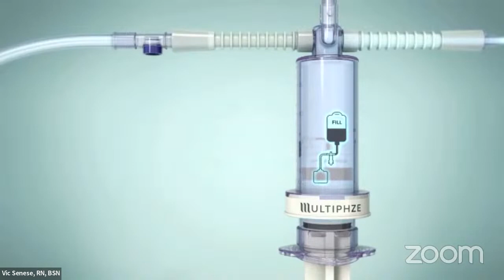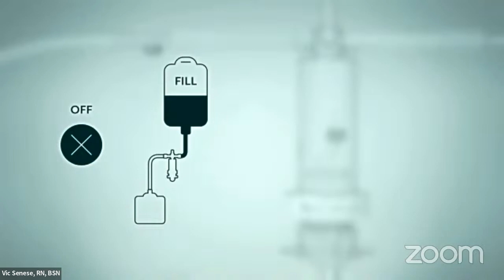The proprietary syringe has an augmented volume of 120 milliliters and 4 independent positions. 1. Off for no flow of fluids. 2. Fill to pull sterile solution into the syringe. 3. Irrigate to push and pull fluids in and out of the bladder from the syringe. And 4. Drain to push fluids from the syringe into the attached drainage bag. The syringe provides icons and labeling, as well as tactile and audible feedback to affirm when the syringe is in each phase. The syringe comes packaged in the irrigate phase.